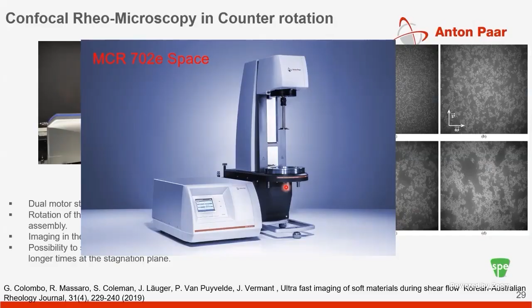And typically, for such applications, we make a unique multi-drive where all the stuff which I talked about still holds, but what is unique about the system is that the electronics, which is typically in the rear side of the rheometer, is actually separated from the device. So now this really opens up new capabilities, because you can butt this rheometer up against a confocal microscope, or you can put it in a glove box, where typically you don't want to put electronics inside. So those types of applications are also possible.